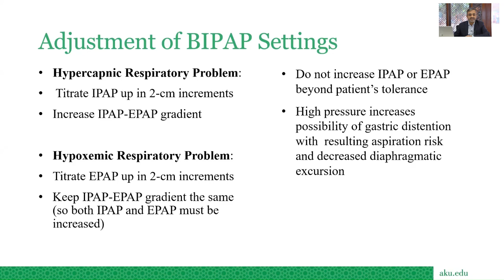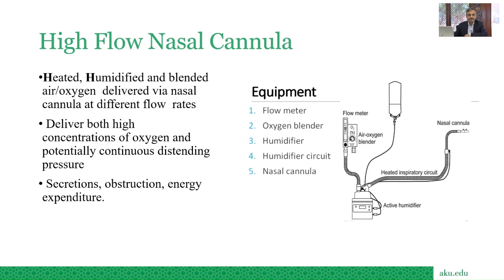High flow nasal cannula basically provides heated, humidified and blended air oxygen delivery via nasal cannula at different flow rates. It delivers both high concentration of oxygen and potentially continuous distending pressure. It aids clearance of secretions, prevents obstruction by delivering distending pressure, and it also conserves energy expenditure by providing heated and humidified air. And on the right hand side, you can see a setup with a flow meter, an oxygen blender, a humidifier, a humidified circuit, and then a nasal cannula, which is the interface in the form of high flow nasal cannula. So initial flow is age dependent.